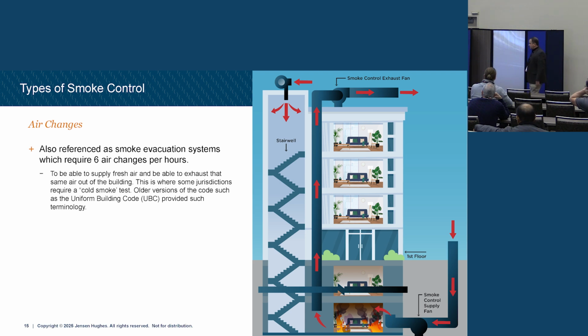The way we would do that is you literally use a smoke bomb, and you put it in a heat generator, and you dump smoke, and then you turn on the air handling system, and you watch it dilute the smoke. And you can measure obscuration and all those things. Not a big fan of these systems, but if they're there, they need to be maintained and tested properly.